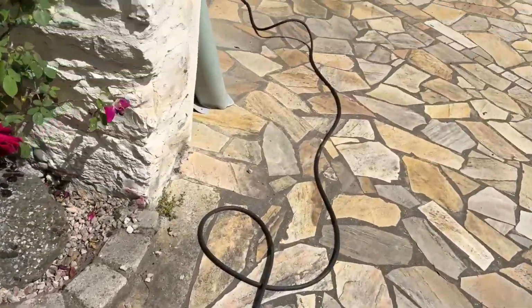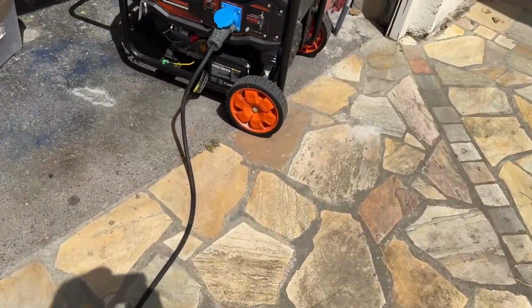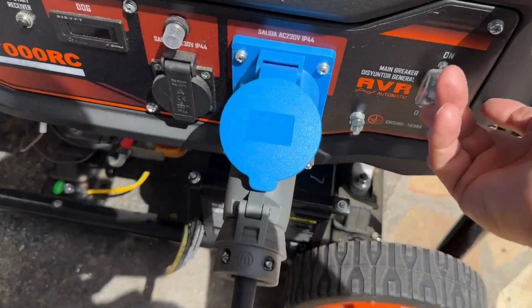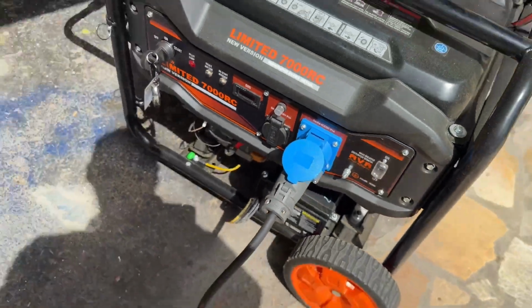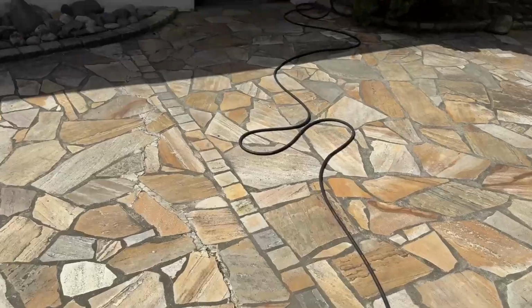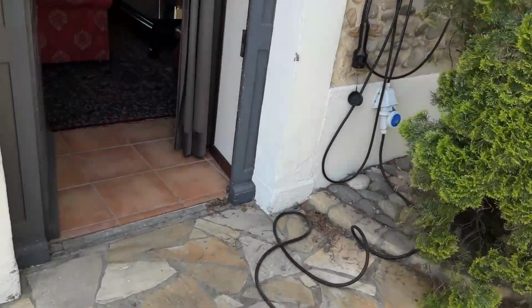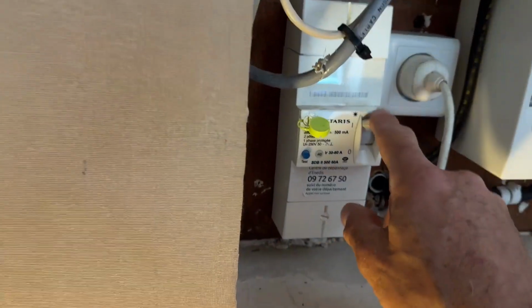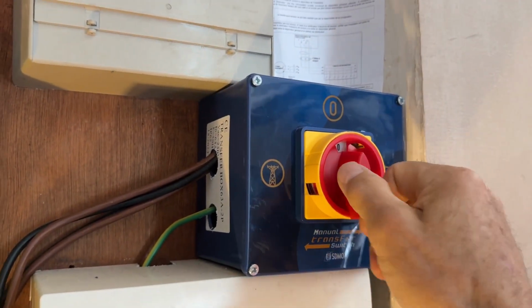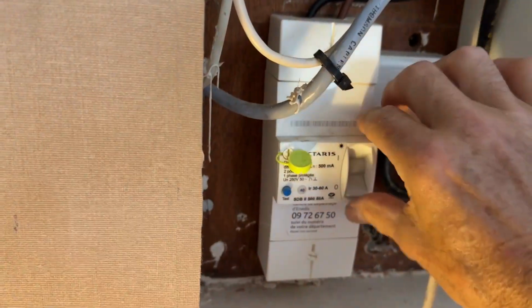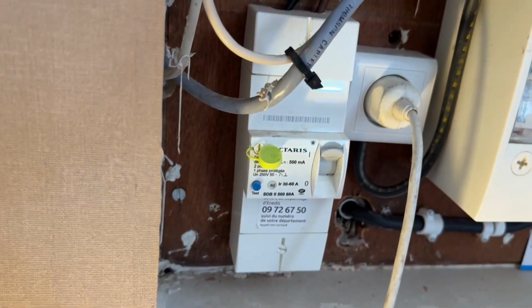We can now close the circuit breaker on the generator. This puts power through the cable to the circuit breaker board in the house. We've got power now all the way down this cable. Now the main circuit breaker, we've opened this first, switched from mains to neutral to generator power, and then closed the main circuit breaker again. And we've now got power from the generator through the cable into the house.